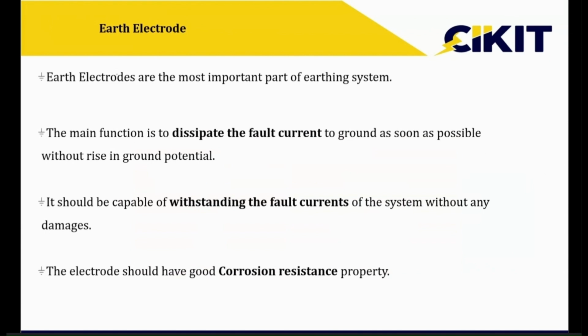The purpose of the earth electrode is to dissipate the fault current into the soil. If it has to dissipate the fault current, then it should be able to withstand the fault current. If it is able to withstand, only then can it dissipate. And apart from this property, the second most important thing is the corrosion resistance property of the material. So aluminum, even though a very good conductor, is not preferable for earthing because of its poor corrosion resistance. So that is also one of the most important parameters required for earth electrodes.